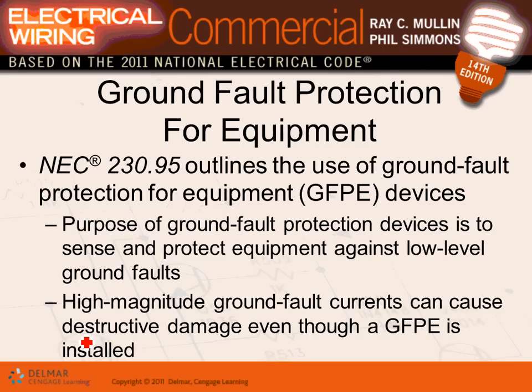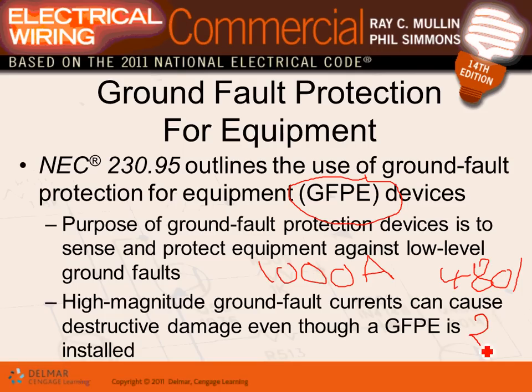There's something called ground fault protection. Ground fault protection is required on any system of 1000 amps or more. So if you don't have 1000 amps, you don't even worry about it. And the voltage is 480/277. Guys, when the voltage is very high and the current is very high, there will be ground faults high enough that they can burn your building, but low enough that the circuit breakers cannot see them and trip.